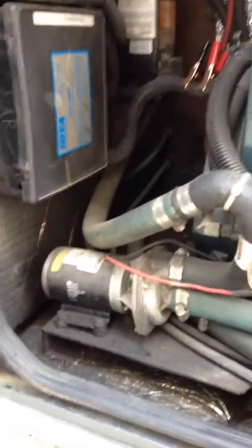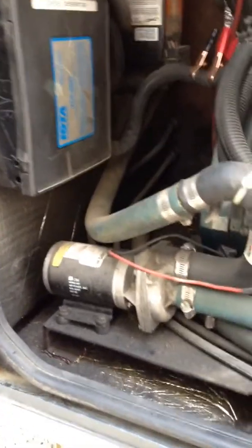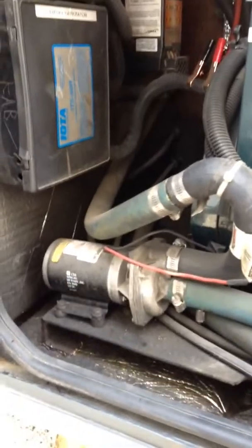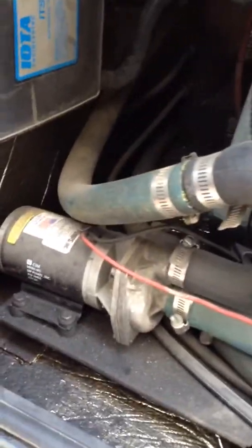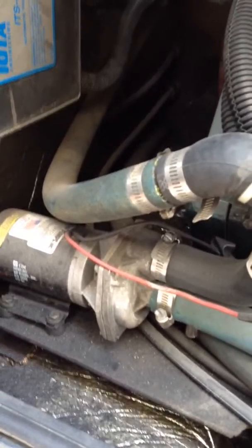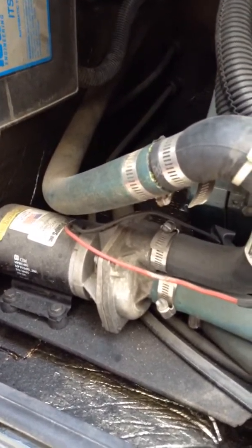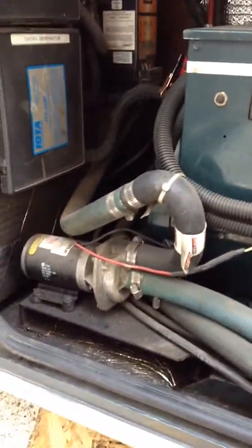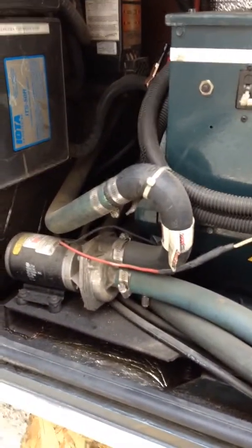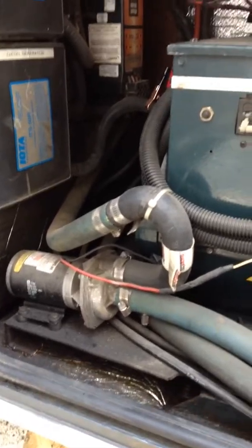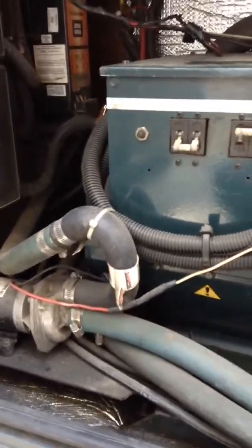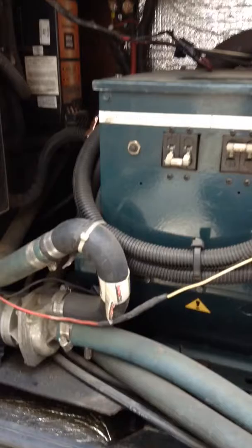Another component that this has is an electric water pump. It also has to be running or you're going to overheat. There's a shaft that sticks right out the end of it right here. It's not sharp. When it's running, you can simply touch that shaft and feel if it is turning. If you confirm that the 3 fans are running and the water pump is running, if you are up on oil and not low on coolant, the generator should run.